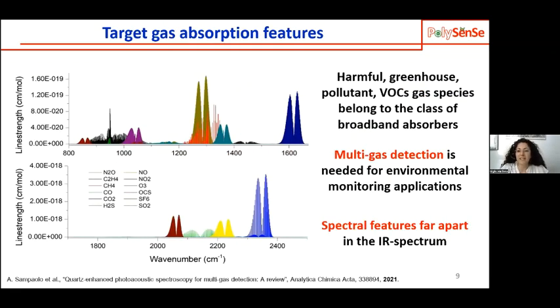In this case, we were targeting just one gas molecule and one absorption line of this molecule. However, often harmful greenhouse pollutants and also volatile organic compound gases belong to the class of broadband absorbers. So, especially for environmental monitoring purposes, multi-gas detection is needed. Often we need to target several absorption lines which are far apart in the infrared spectral range. So we need a multi-gas detection technique. Quartz-enhanced photoacoustic spectroscopy is a multi-gas detection technique because, as I already showed you, the responsivity of the detector is flat, and it does not depend on the wavelength of the laser source.